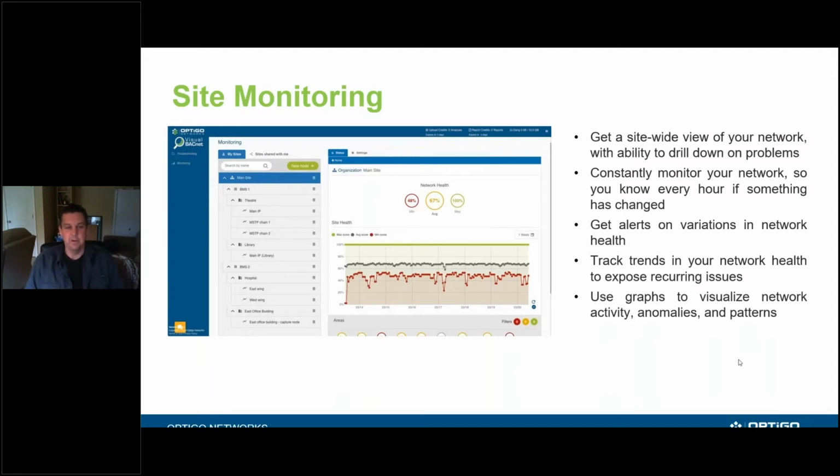Because you're constantly monitoring every hour, you now get an hour's worth of granularity. So something that happened over the weekend isn't all that helpful in a 72-hour period, but something that happened on Saturday night at 1 a.m., that does help you. And it allows you to refer back to your BMS, possibly trend logs or your archiver, and see what's in there and see what changed.